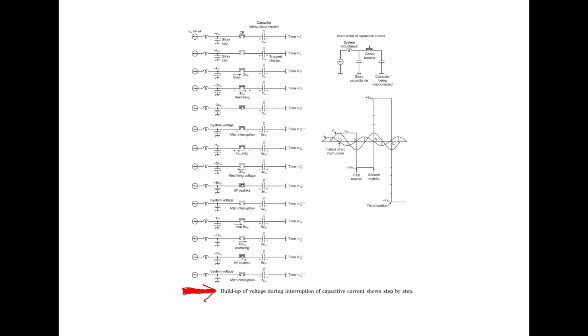So the voltage across the circuit breaker contact in this case, if you use the KVL, is 0, and the successful interruption takes place at the instant T1, with the result that capacitor C is left with the trapped charge corresponding to the voltage Vm. Now, the right hand side of the circuit breaker is held at the potential of plus Vm, while the left hand side swings along the system voltage.